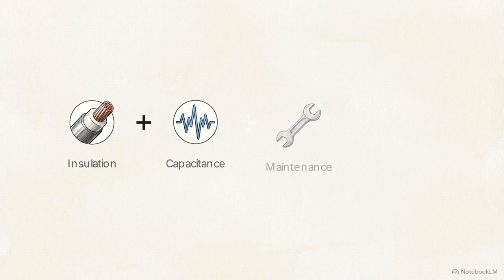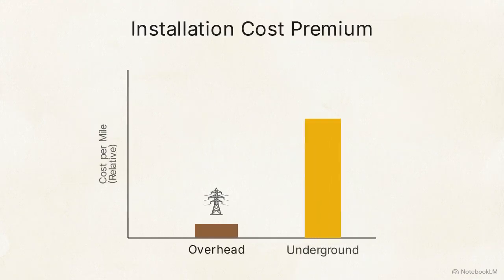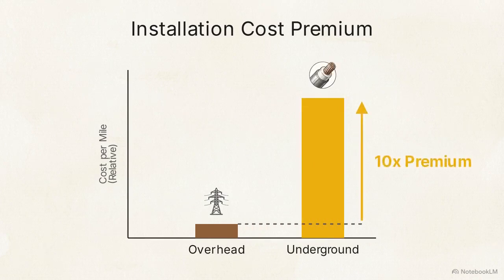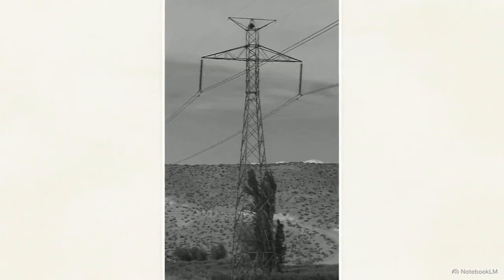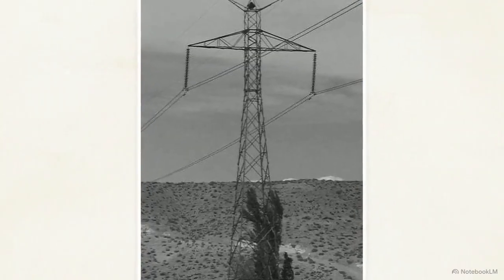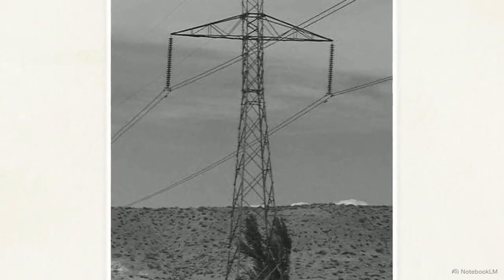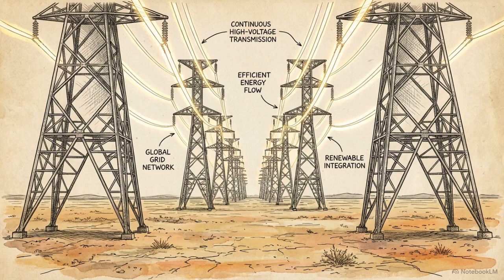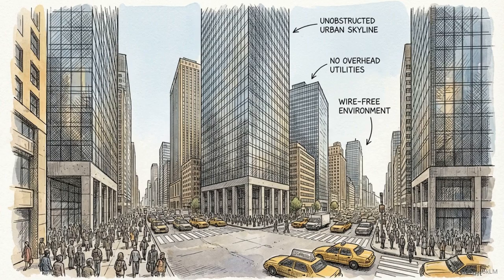When you combine the need for heavy insulation, the physics of charging currents, and the extreme difficulty of maintenance, the math becomes unavoidable. Installing an underground cable routinely costs anywhere from 3 to 10 times more per mile than building an equivalent overhead transmission line. This is why overhead lines dominate rural areas and long-distance transmission. Open air is a free insulator, capacitance is near zero, and the physics of moving power over hundreds of miles remain efficient. Underground cables are strictly reserved for dense urban networks.